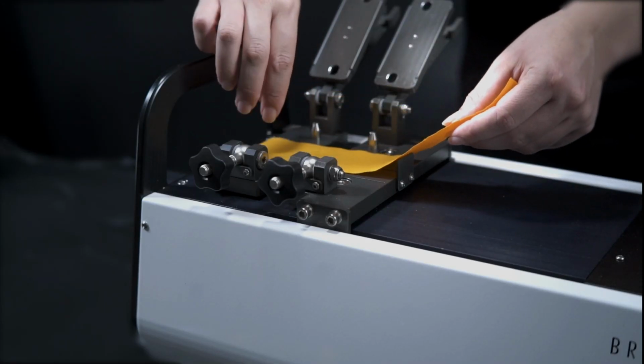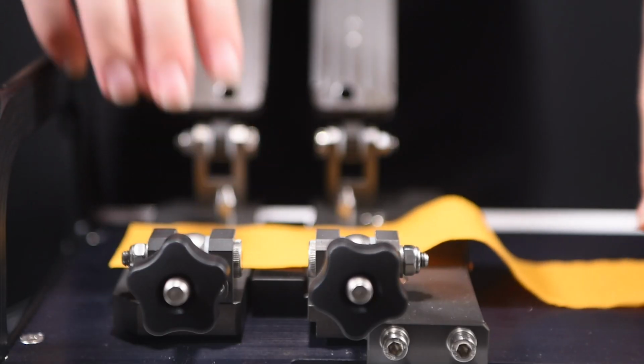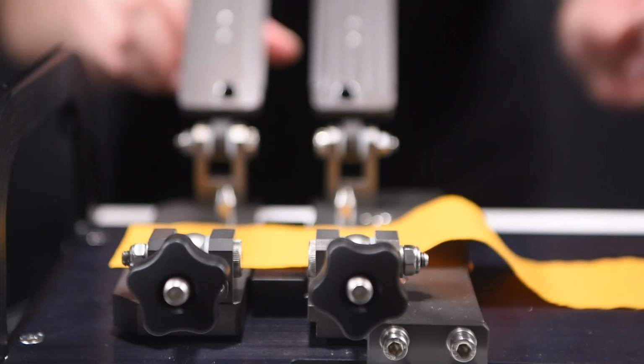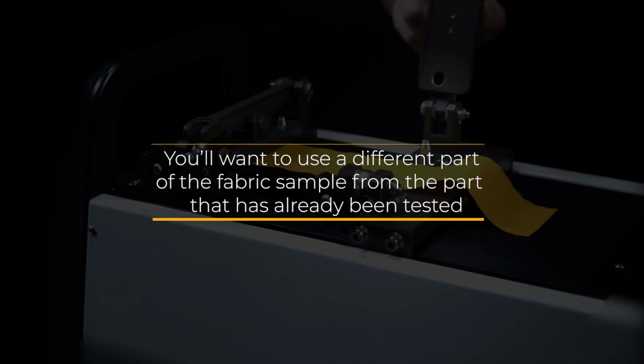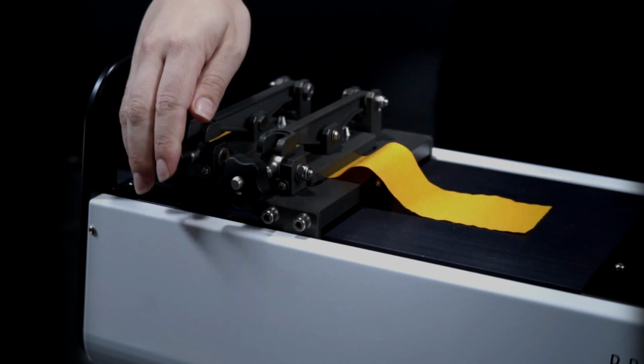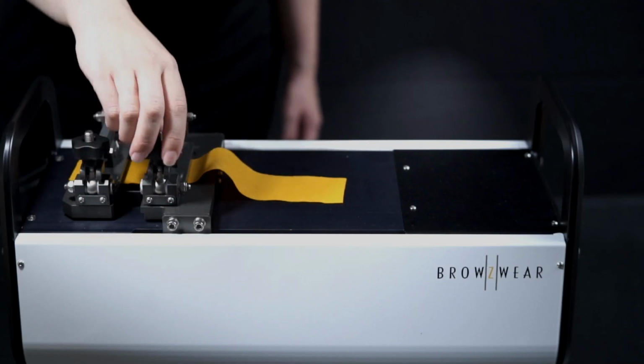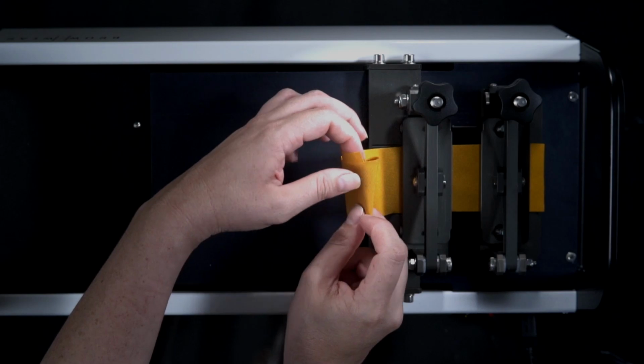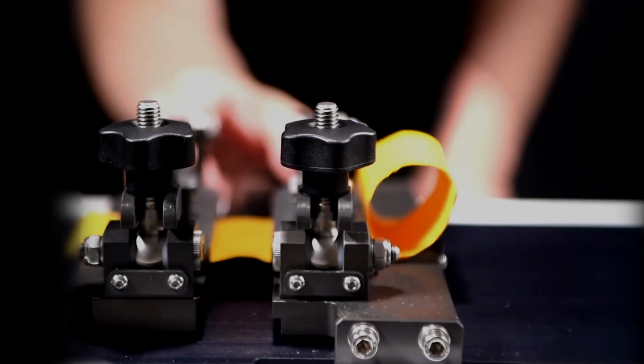Lay the fabric down with the short side of the sample aligned with the left side of the fixed clamp. Note, you want to use a different part of the fabric sample from the part that has already been tested. Close both clamps, pulling each screw head up and tightening it.